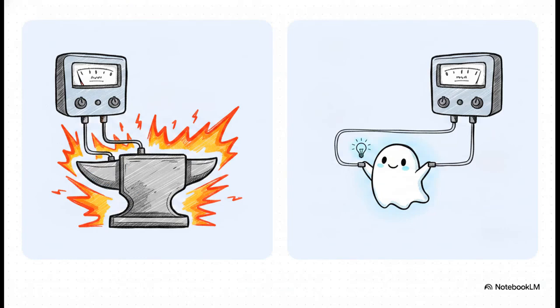But honestly, the most brilliant reason for this missing internal connection comes down to simple economics and heat management during calibration. Let's say you need to test if a 220-volt 5-amp watt meter is perfectly accurate. If you test that on a real physical load of full capacity, you are wasting over 1,000 watts of power as pure heat. That's basically running a heavy-duty space heater for no reason, and that heat can actually warp your delicate test results. But by separating the M and C terminals, engineers invented a clever workaround called phantom loading, which drops that wasted power down to just 50 watts.